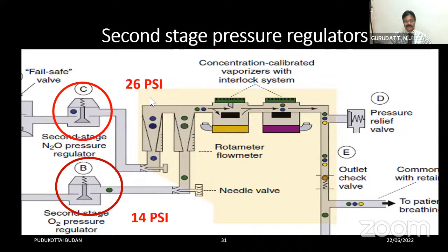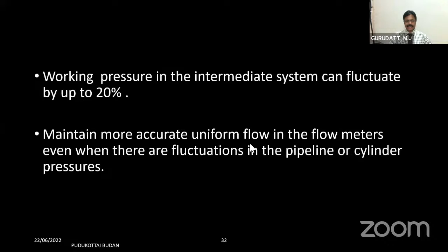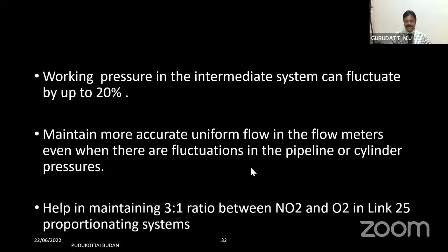So this is going to help the Link 25 system maintain a 3:1 ratio between nitrous oxide and oxygen. That is the proportionating devices that are present in GE machines, which I'm going to discuss later. The second stage pressure regulators also help in maintaining the 3:1 ratio between nitrous oxide and oxygen. So the Link 25 is almost purely mechanical, almost 95% mechanical. Some amount of pneumatic component is also there because of the second stage pressure regulators.